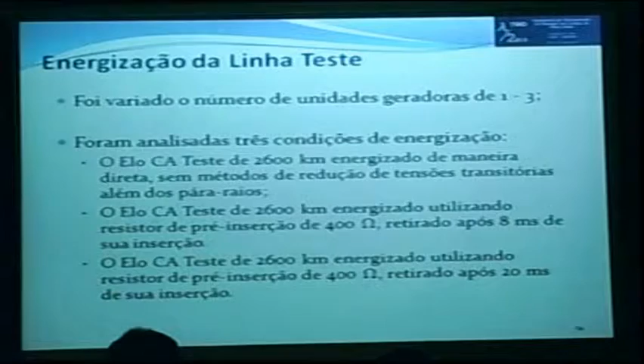So if the resistor is maintained only for 8 milliseconds, it does not act for the wave that is coming back. But to compensate, on the other hand, 20 milliseconds was not what it was designed for, so we needed to check the impact of that. So for direct energization, here I present the results of the overvoltages. They are smaller with 3 generator units, so when the short circuit power is higher, the system will have a better response. But with 1 generator unit, we're going to have an overvoltage a little above 1.8.